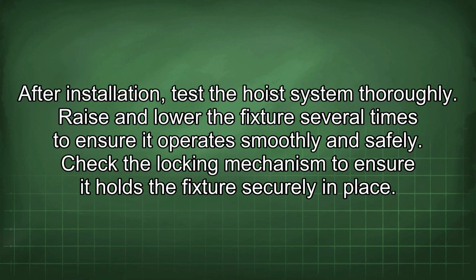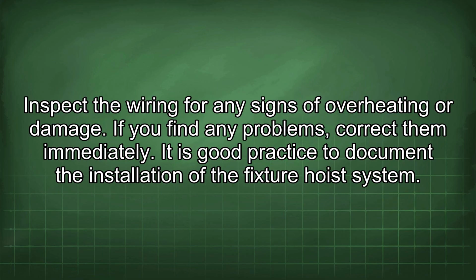After installation, test the hoist system thoroughly. Raise and lower the fixture several times to ensure it operates smoothly and safely. Check the locking mechanism to ensure it holds the fixture securely in place. Inspect the wiring for any signs of overheating or damage. If you find any problems, correct them immediately.